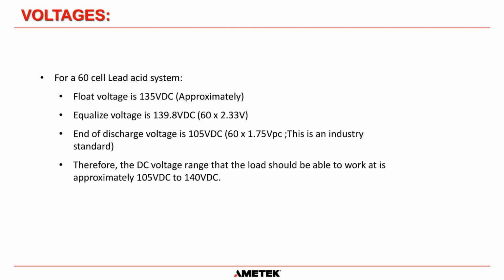So for a lead acid system, the float voltage is approximately 135 volts DC. And we'll go into some different manufacturers. The float voltage is the voltage that we need to charge the batteries at, that overcomes all of the chemical losses within the battery and keeps them charged correctly without overcharging them. It's manufacturer specific, but as a general rule, for a 60 cell system, it is around 135 volts DC. Equalized voltage is usually 2.33 volts per cell. So if you multiply that by 60, it comes out at 139.8 volts for equalize.